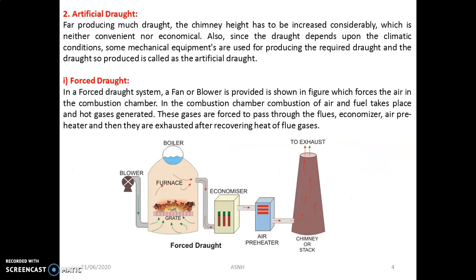The second important type, mostly used in large capacity power plants, is artificial draft, where the generation capacity of steam is very large. There are again two types: forced draft and induced draft. The basic difference between them is that in forced draft a blower is placed before the furnace, while in induced draft that blower is placed just before the chimney.